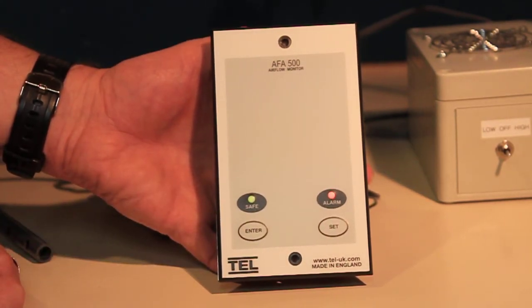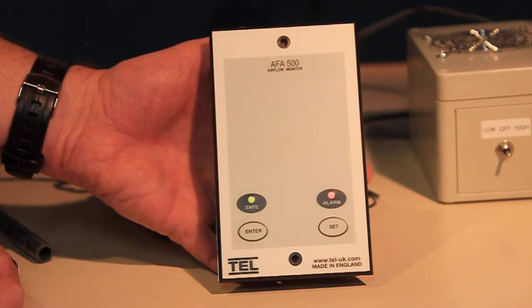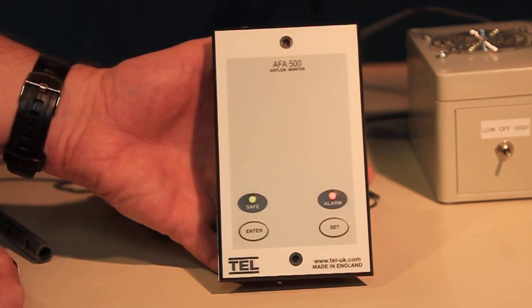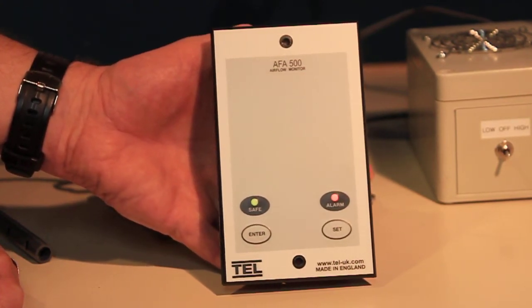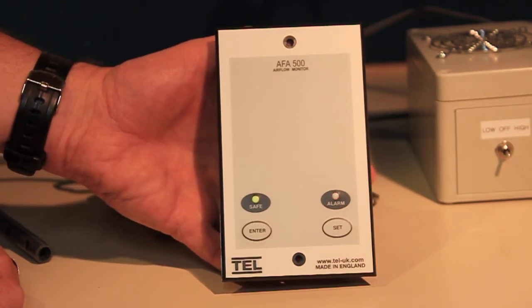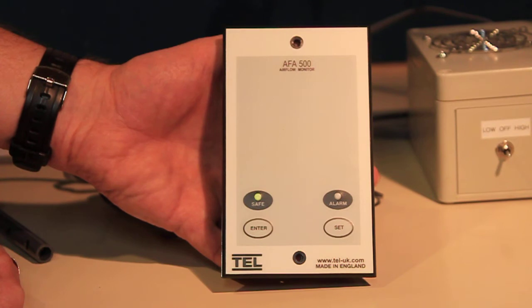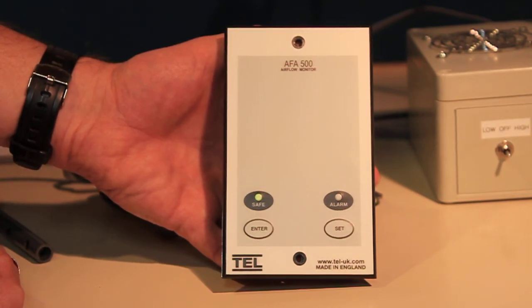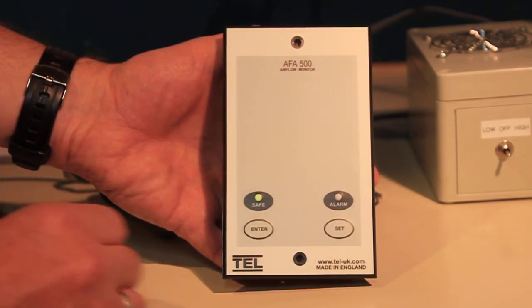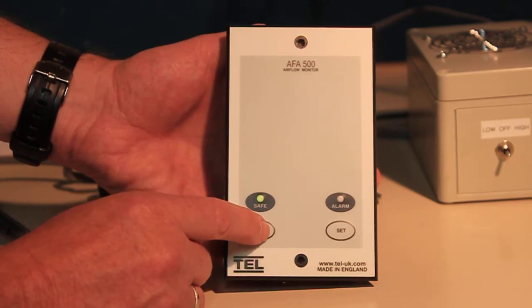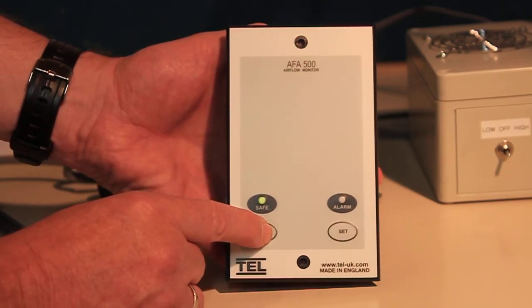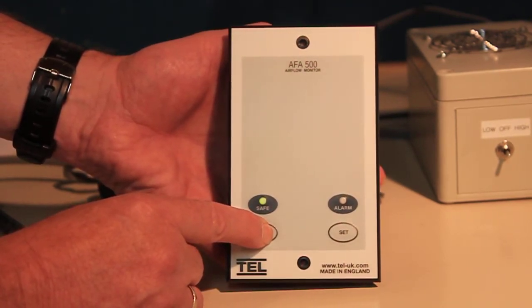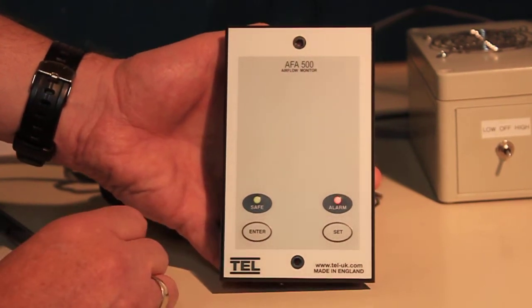In a laboratory setting, the monitor should be calibrated in normal operating conditions after the laboratory's air has been balanced and tested. Using the conventional single-point process, the calibration will establish the monitor's low air alarm value as a 20% reduction from the measured airflow. Press and hold the Enter button for 5 seconds to enter calibration mode. This is indicated by both red and green LEDs flashing with the audible alarm beeping.